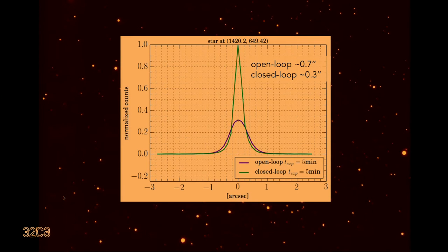And this is over a huge field. So the correction is not just in the middle, but you can see also at the very edges of this image, we do see this improvement in image quality. Of course, you can have the diagram if you want. The blue line is without the system being activated, open loop. And if we close the control loop to do this measurement and correction in real time, we squeeze all the energy into very few pixels, which of course also means our signal-to-noise level in a single pixel goes up tremendously, meaning you can decrease your exposure time, which is important.